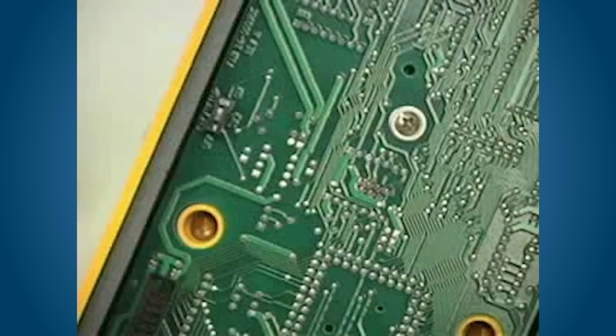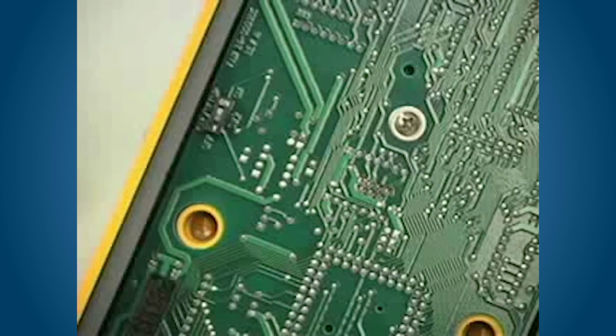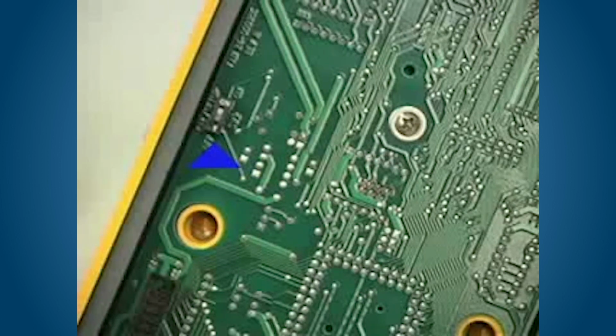As a security feature, the Eagle is equipped with an adjustment lockout switch, also known as the Cal setup switch. This switch can be set to prevent users from having access to the calibration and setup menus of the Eagle. The adjustment lockout switch is mounted near the middle left edge of the main PCB and is labeled SW2.